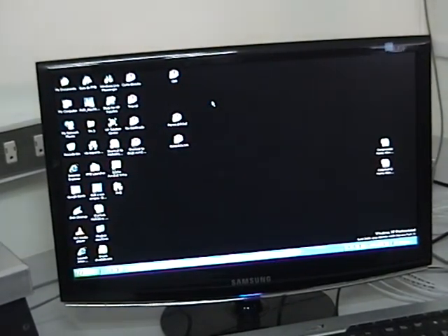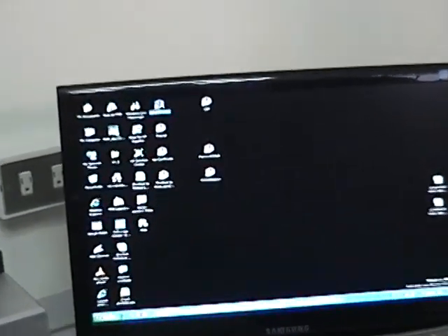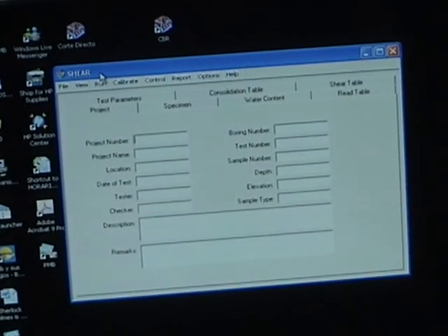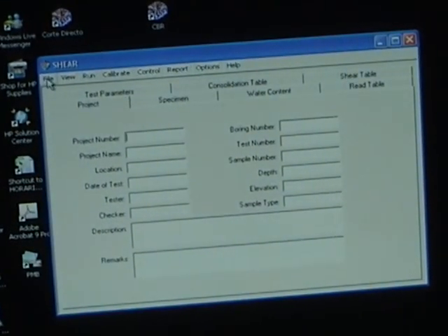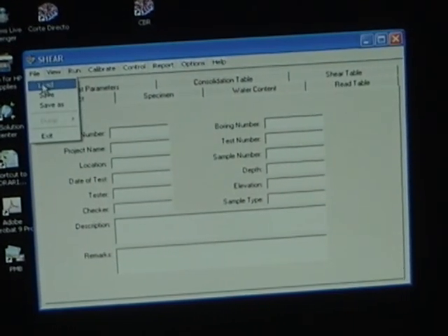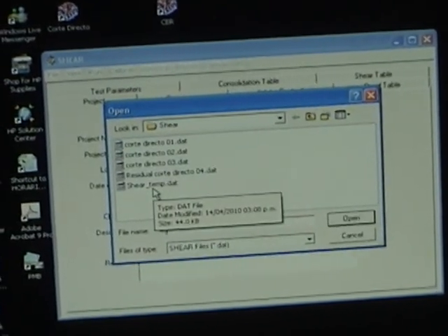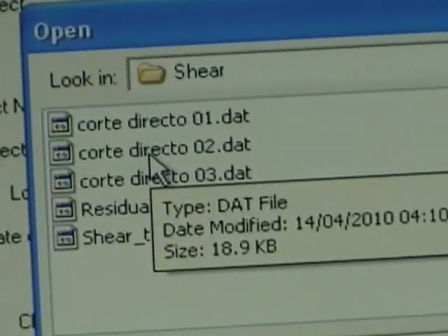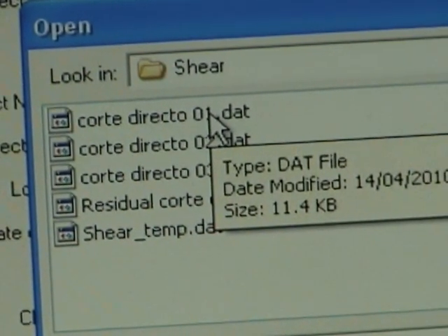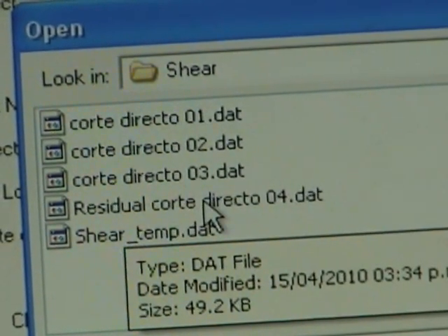Next we are going to load the software, set our testing parameters, and run the test. We go to the software for Corte Directo. The first thing — very important — we go to File, we do Load, and we're going to load a template file. This is a template, or we can load a test that was run previously and use it as a template file. Now we're going to run this residual test as a template.